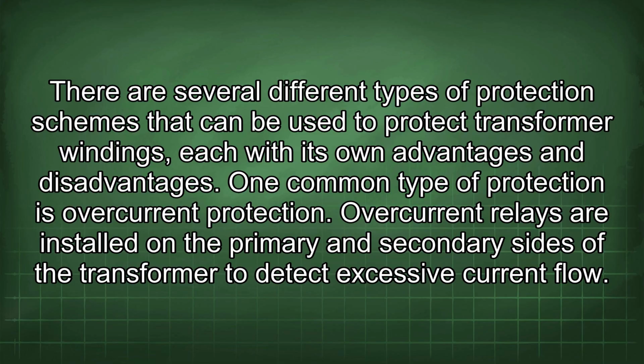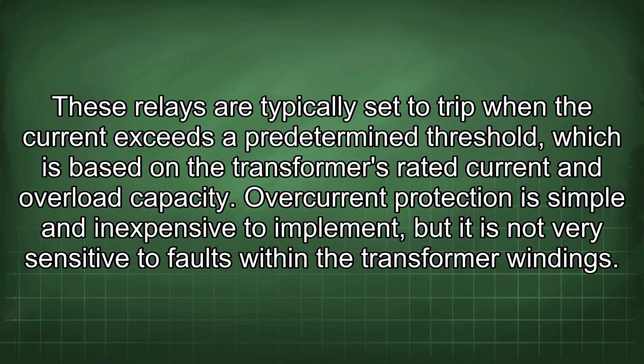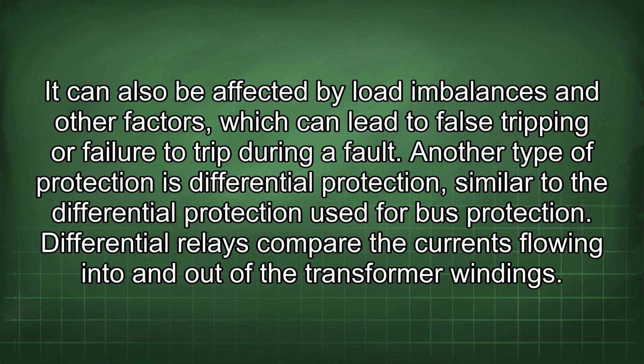One common type of protection is overcurrent protection. Overcurrent relays are installed on the primary and secondary sides of the transformer to detect excessive current flow. These relays are typically set to trip when the current exceeds a predetermined threshold, which is based on the transformer's rated current and overload capacity. Overcurrent protection is simple and inexpensive to implement, but it is not very sensitive to faults within the transformer windings. It can also be affected by load imbalances and other factors, which can lead to false tripping or failure to trip during a fault.